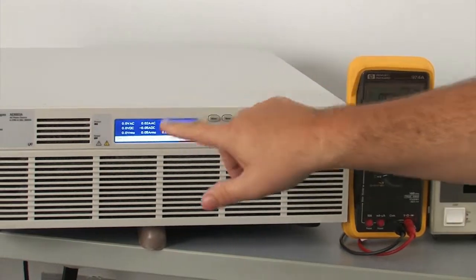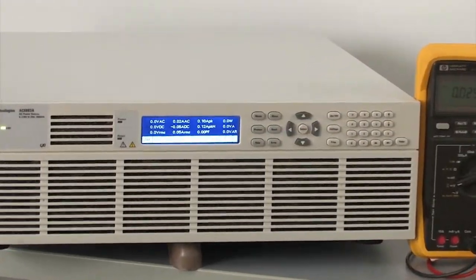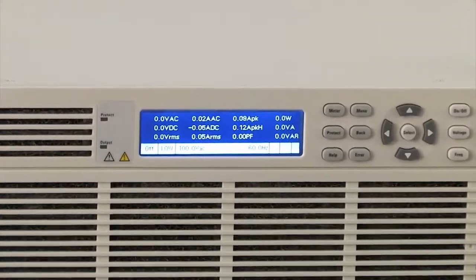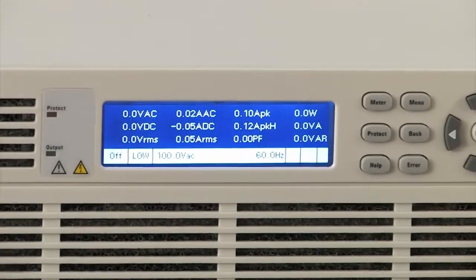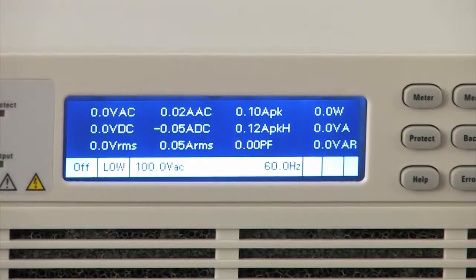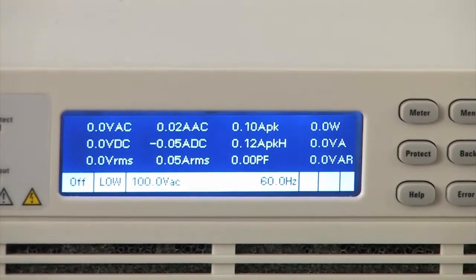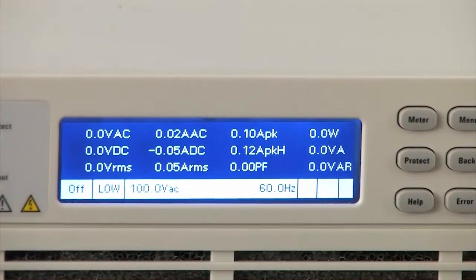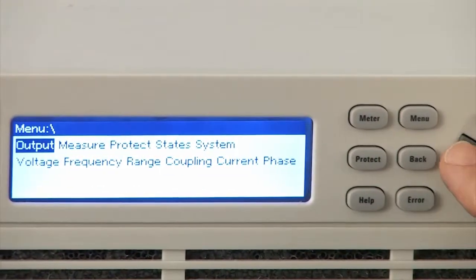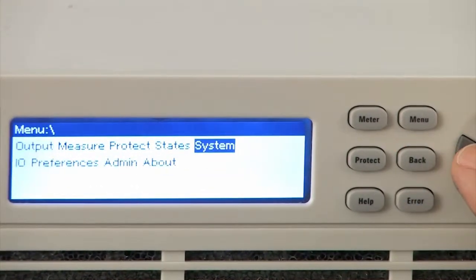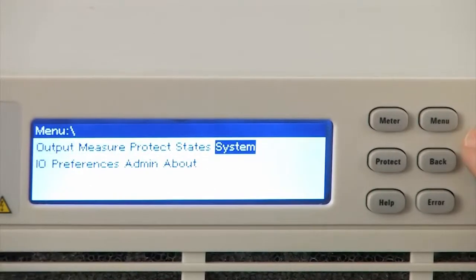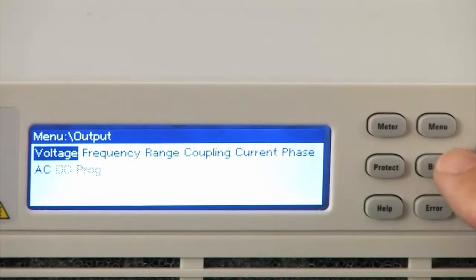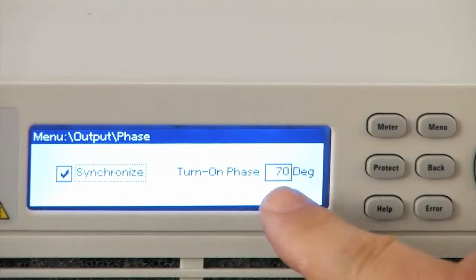With our AC6800 family AC source, I've already set it up for the correct input voltage, frequency, and I've already determined that the worst case inrush current happens at 70 degrees phase angle. This can be set to any phase angle you want using our function keys where you can set the output phase at turn on.